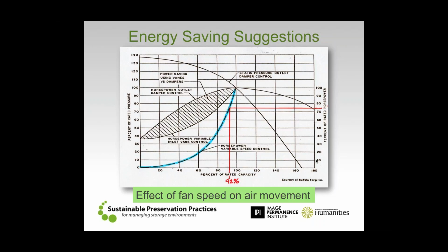Now, it's awfully hard. Many VFDs won't actually dial down quite that far. You still have a limit in terms of how they can operate. But it's this idea that you want to consider. I would argue that there are a number of spaces out there, especially in terms of storage, where for a good percentage of the year, you could probably reduce that total airflow down to 80% or 75%. And notice that if we did that, maybe we're only looking at roughly saving 60% of the total energy that we were using before.